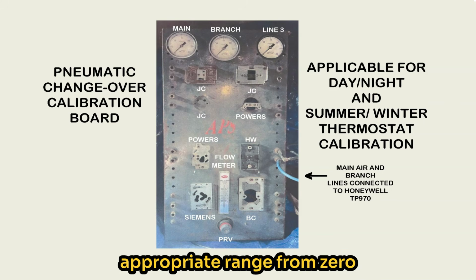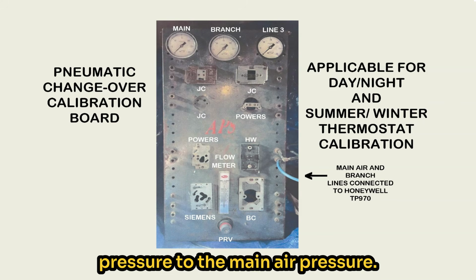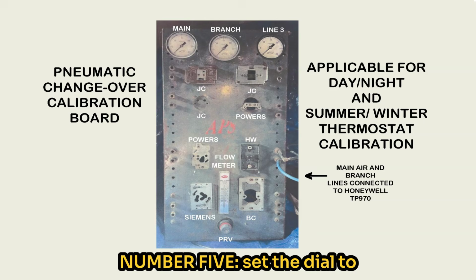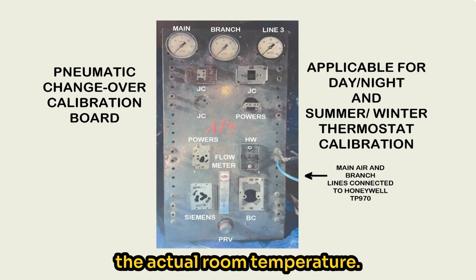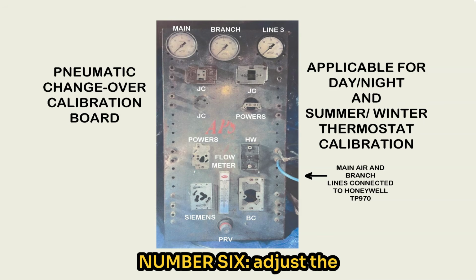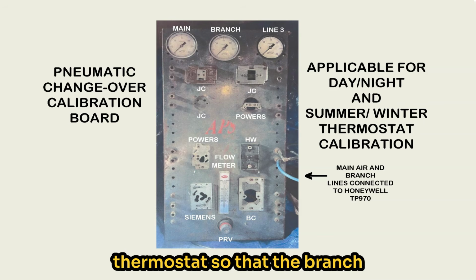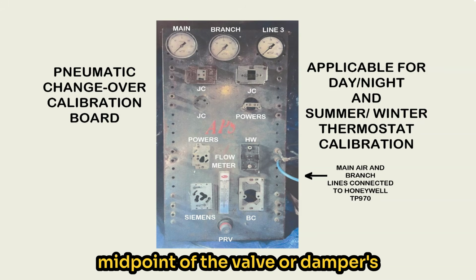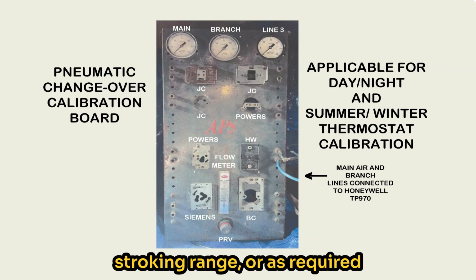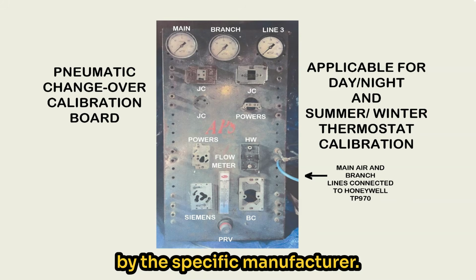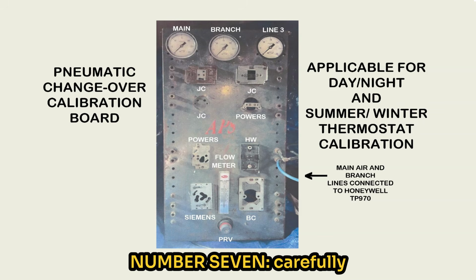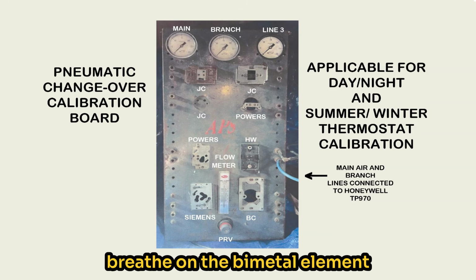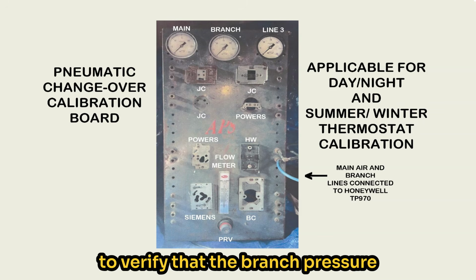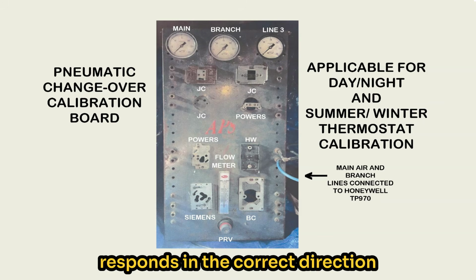to respond through the appropriate range from zero pressure to the main air pressure. Number 5, set the dial to the actual room temperature. Number 6, adjust the thermostat so that the branch pressure is approximately midpoint of the valve or damper's stroking range, or as required by the specific manufacturer. Number 7, carefully breathe on the bimetal element to verify that the branch pressure responds in the correct direction.